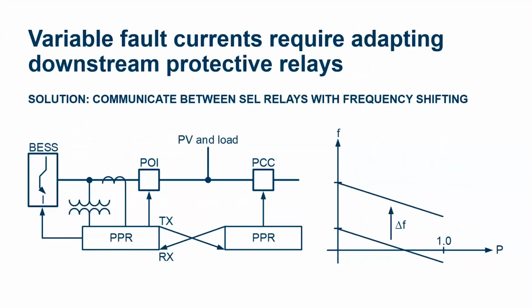When you have a variable fault current system, such as in this case a distribution feeder circuit with a battery energy storage system, a BESS, it has a point of interface breaker and a point of common coupling breaker, and it has many breakers down the distribution line. But we don't have a communication network 20 miles down the line to tell those reclosers and breakers, hey, you need to adjust and adapt your protection based upon the fact that now you aren't connected to the utility. You're connected to a battery, because that battery can't produce the fault current of your local utility. How do we fix that?